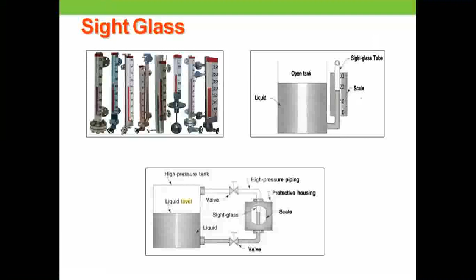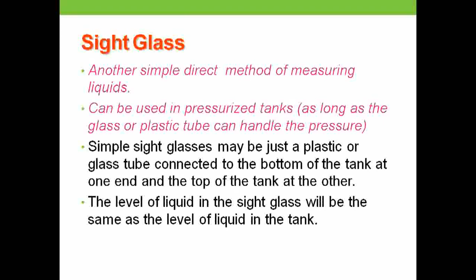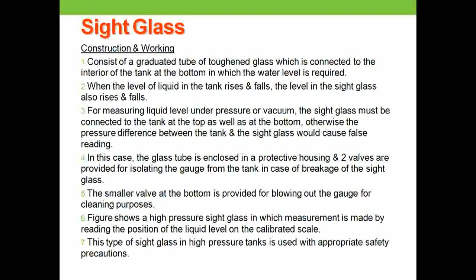Both the tank, which is in open contact, and the sight glass tube, which is indicating our level measurement, will be at normal atmospheric conditions. So both the tank holding the liquid and the sight glass which is measuring will be released to the atmospheric conditions. The sight glass is a method of measuring liquids and is used in pressurized tanks, high pressure tanks, which hold a maximum quantity of the liquid. This is the construction that we have already visualized in the diagram also.